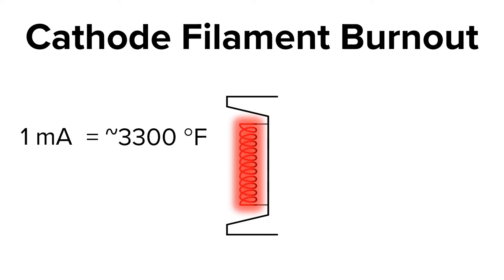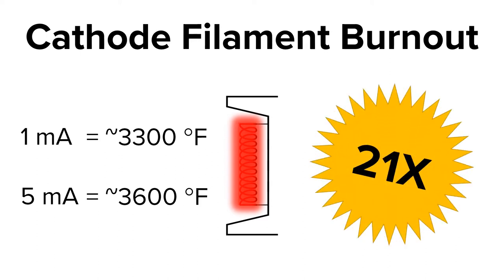But if you make an exposure at 5MA, you're heating the filament to about 3,600 degrees Fahrenheit. This 300 degree difference between 1MA and 5MA causes the filament to burn out 21 times faster. High heat is the number one cause of cathode filament burnout.